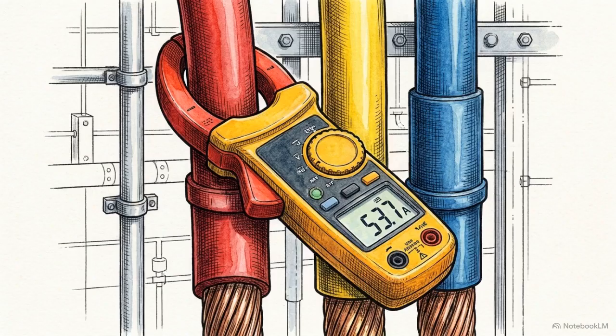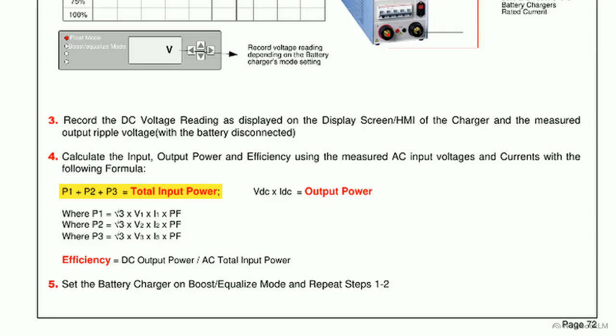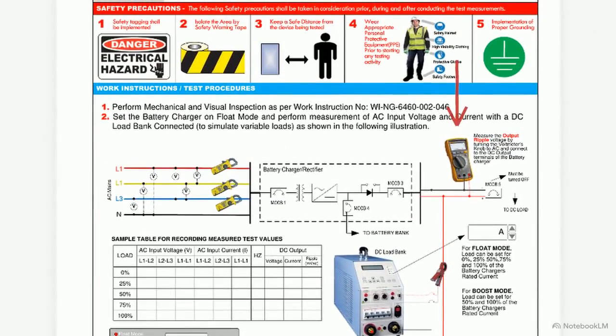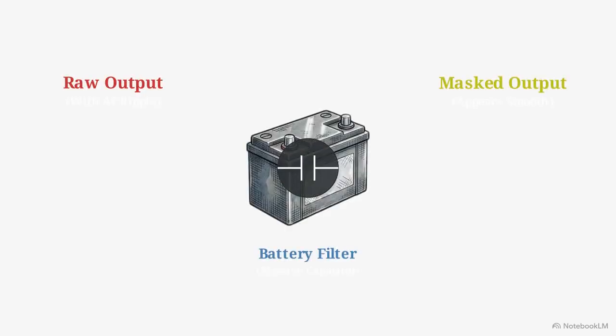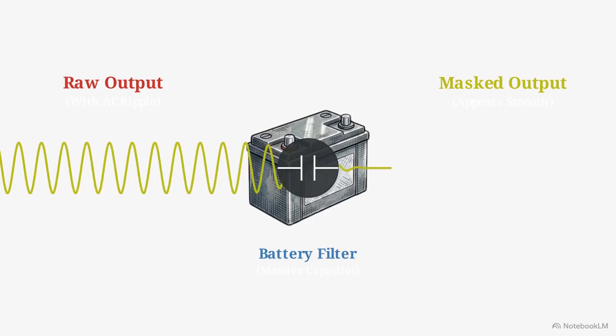At every single one of those load steps, technicians measure the 3-phase AC input voltages and currents. The manual details calculating total AC input power from 3-phase measurements. Comparing DC output against AC input derives overall efficiency. It also highlights measuring DC output ripple voltage, requiring a multimeter on DC terminals set to read AC. Crucially, the battery itself must remain mechanically disconnected during this step. A connected battery acts as a massive capacitor, which would smooth out the ripple and skew the true output results of the charger.